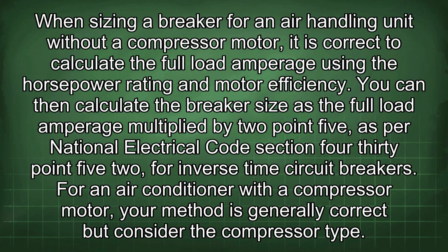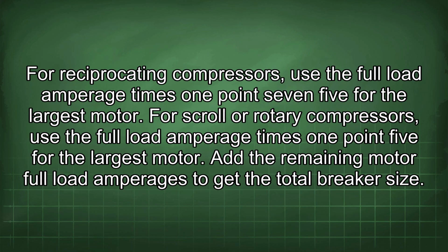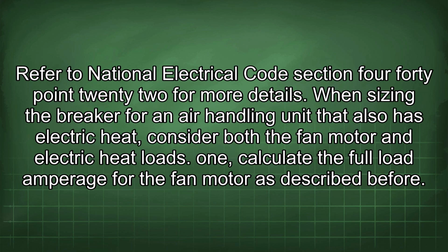For an air conditioner with a compressor motor, your method is generally correct, but consider the compressor type. For reciprocating compressors, use the full load amperage times 1.75 for the largest motor. For scroll or rotary compressors, use the full load amperage times 1.5 for the largest motor. Add the remaining motor full load amperages to get the total breaker size. Refer to National Electrical Code Section 440.22 for more details.